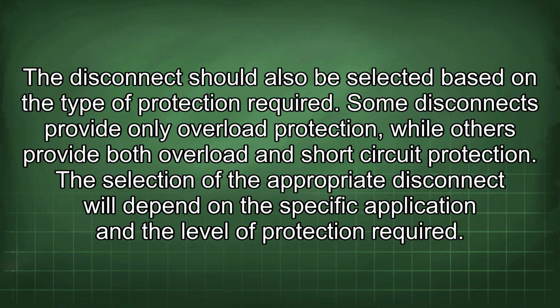The disconnect should also be selected based on the type of protection required. Some disconnects provide only overload protection, while others provide both overload and short circuit protection. The selection of the appropriate disconnect will depend on the specific application and the level of protection required.